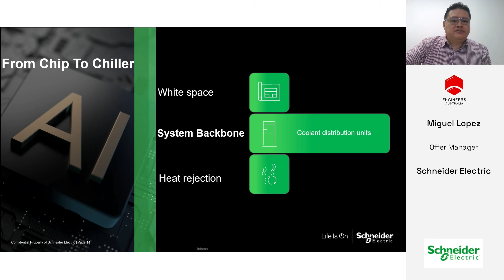Moving along to the backbone of chip-to-chiller architecture, the cooling distribution unit, otherwise known by the acronym CDU. It is the one that is transferring the heat. This particular slide, and you will be getting a copy of this slide deck, I'm pretty sure, shows how the CDU, as you can see on the left-hand side of this slide, is the one recirculating the fluid to and from the server, either single-phase, as we explained, or two-phase fluids. This CDU then has the opportunity either to reject the heat it has captured from the server to the air, in which case the CRACs, CRAHs, in-rows, etc. will remove the heat. These are so-called liquid-to-air CDUs. However, the predominant player in the market as of May 2025 is liquid-to-liquid CDUs.